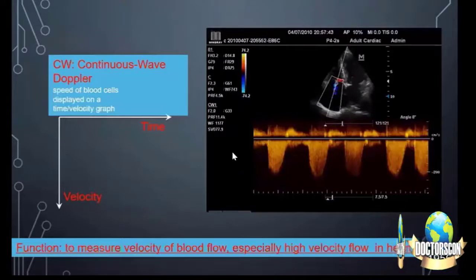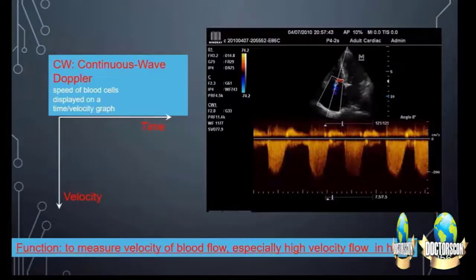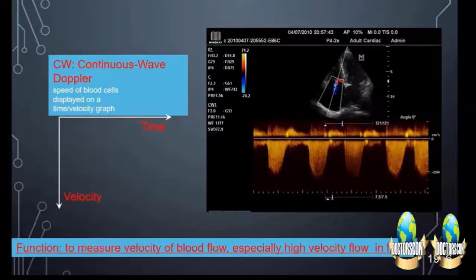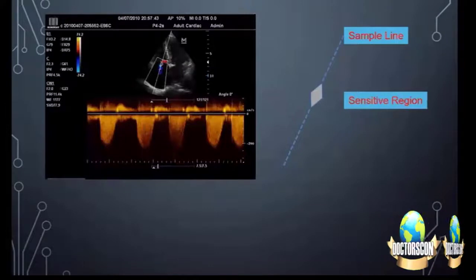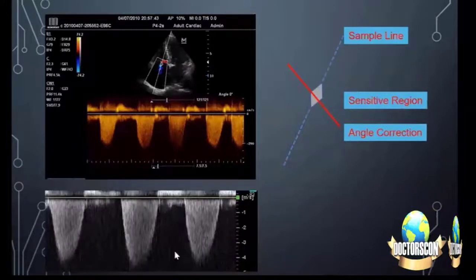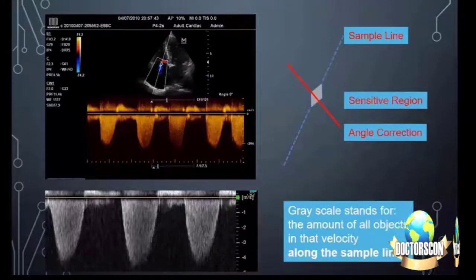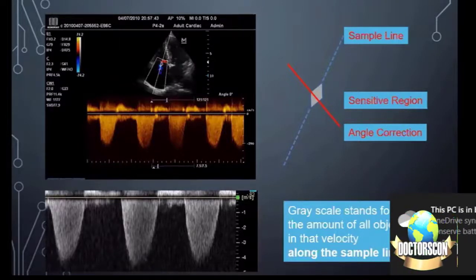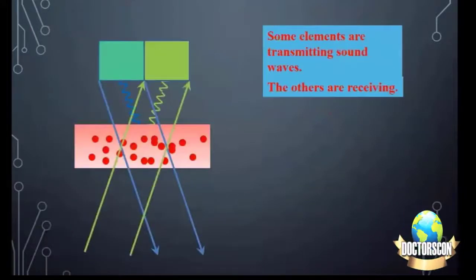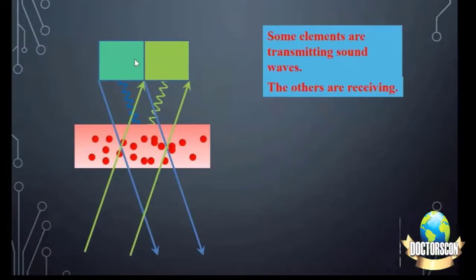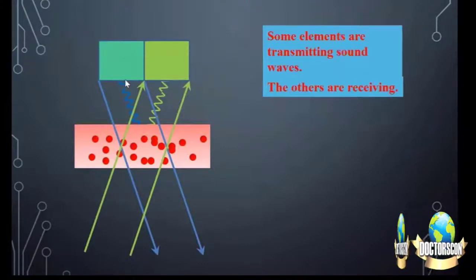In continuous wave Doppler, the speed of blood cells is displayed on a time versus velocity graph. Its function is to measure the velocity of blood flow, especially high velocity flow. We use continuous wave Doppler. This is the sample line, sensitivity region, angle correction, and we get the CW. The principle of CW is that some elements are transmitting sound waves and the others are receiving. So there are two parts of elements. Some elements are continuously emitting, and almost 50% are receiving, so it is going on continuously.